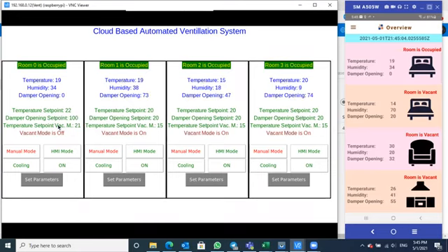Okay, the app worked, and the damper opening set point is 100% as shown here, and I see the damper has been opened to 100%, but it takes a little while to show this damper opening percentage on the HMI.